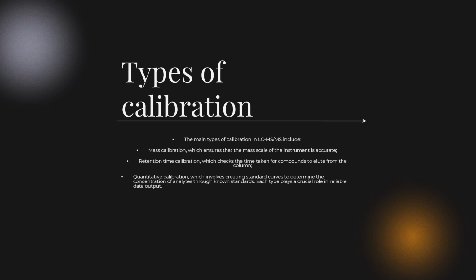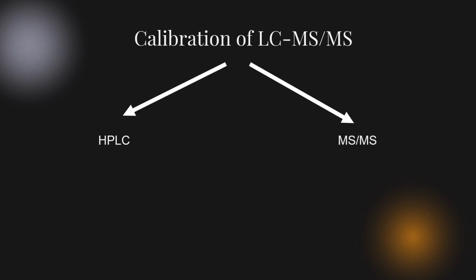Now the main types of calibration of LCMS are mass calibration, retention time calibration, and the calibration curve, that is the correlation coefficient. To simplify the calibration of liquid chromatography mass spectroscopy, it can be divided into two: you need to calibrate the HPLC and the detector, that is mass spectroscopy. It can be divided into these two parts.